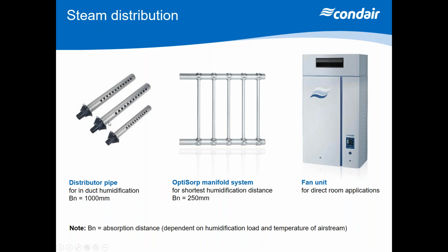When we talk about steam distribution, how do we get the steam into the duct? Well, very simply, it's a stainless steel tube with holes in it. Flexible steam hose will connect to this port, and the tube will be mounted onto the side of the duct or air handling unit, and then steam will come out of these holes. The thing we have to consider is the absorption distance. So how long will it take for that steam to be completely mixed with the air? And that will depend on a number of factors: air-on temperature, duct dimensions, velocity, the number of holes in the steam pipe, various other factors. Typically, you're going to see absorption distances around 1 to 1.4 meters.